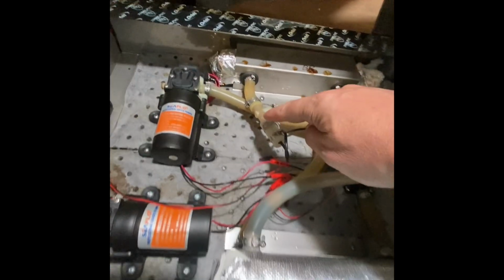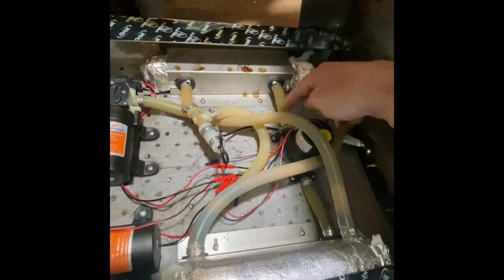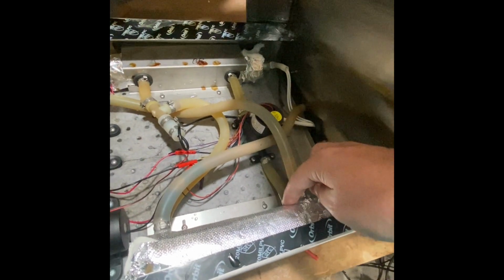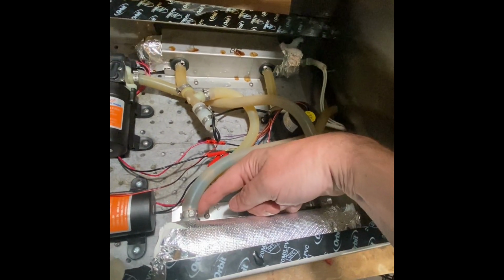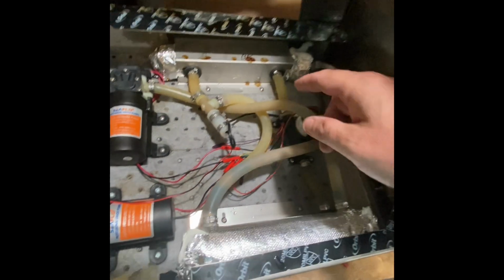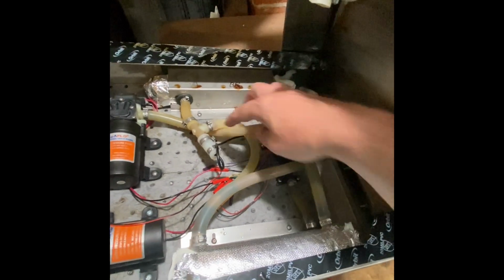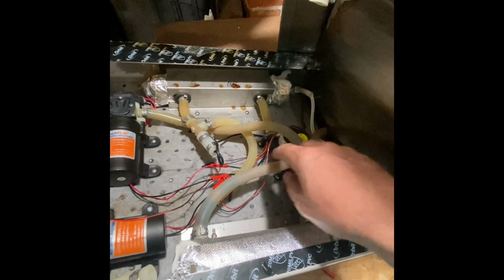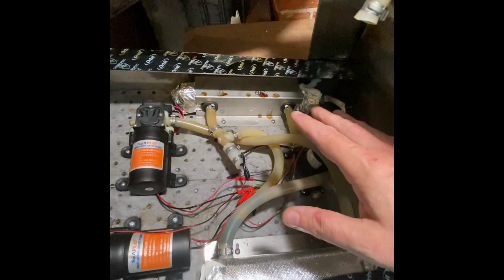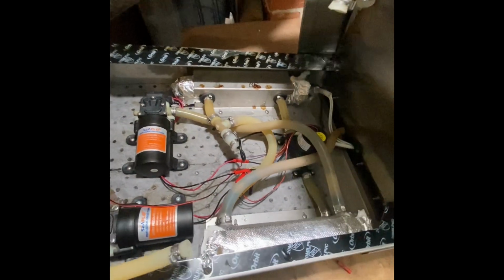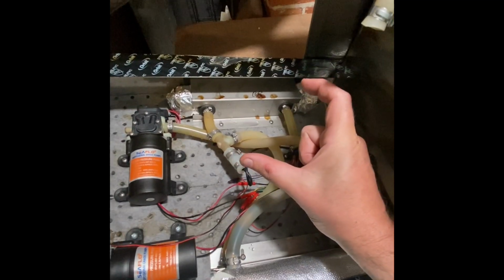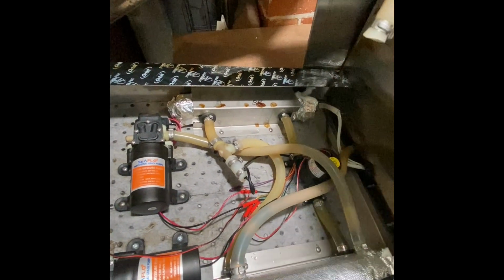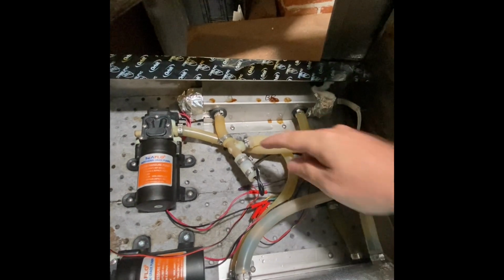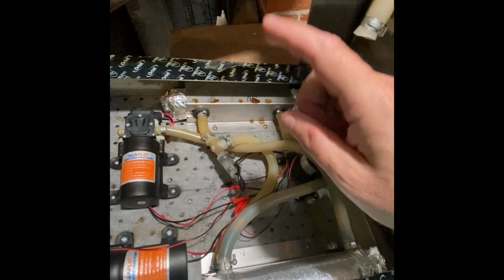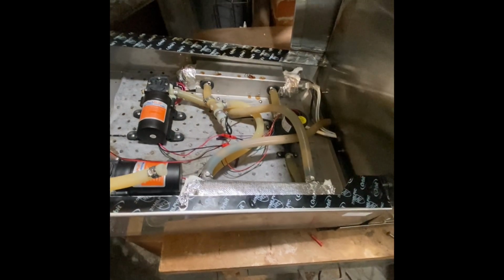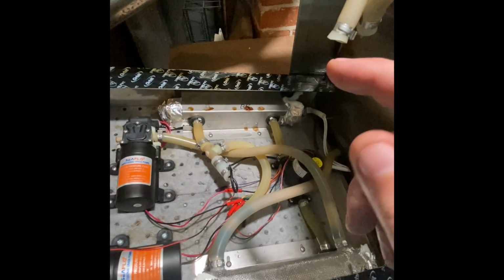Okay, so basically you want to inject the water in here. The water will go in here, through this thing, through there, go in here, then come out here on the bottom one, and it goes in here. This is the path of the heat exchanger. This is a circulating line here. But the heat exchanger itself cannot have any air bubbles in it because, like I said, there's going to be a temperature differential - too much of a temperature difference, or delta, whatever fancy words you want to use, between the heat exchanger, which this sensor is picking up, and the rest of the system. It happens really quick because these heat exchangers heat up things pretty quick.